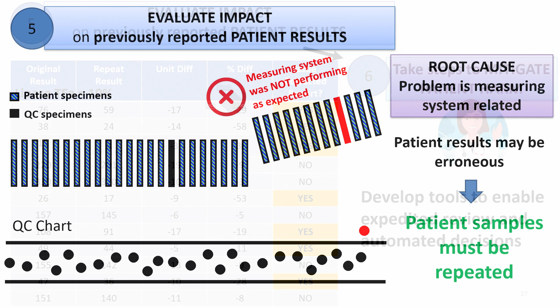So we developed this little tool. It's basically just an Excel spreadsheet. In the first column, the techs can put in their original result, and then they can enter the repeat result. The tool calculates the difference between the repeat and the original result and compares it against an allowable error. For lipase here, I've set the allowable error to 10%. If the difference exceeds 10%, then there's a little script that instructs the tech, yes, please issue a corrected report. If the error does not exceed the allowable error, the script says, no, do not issue a corrected report.